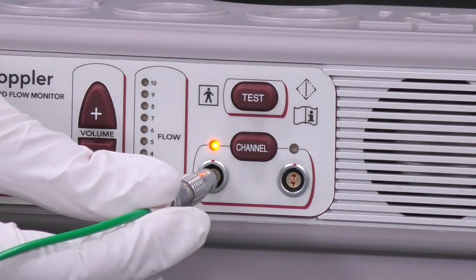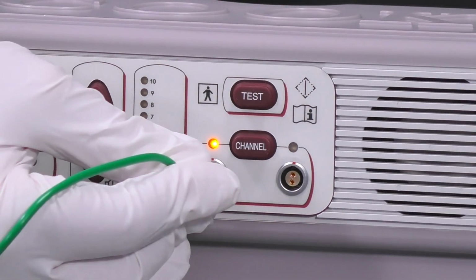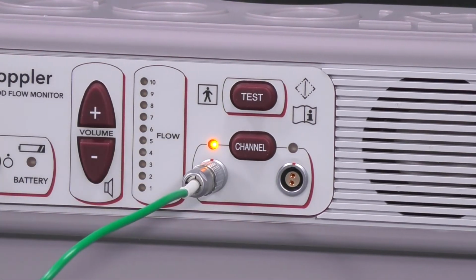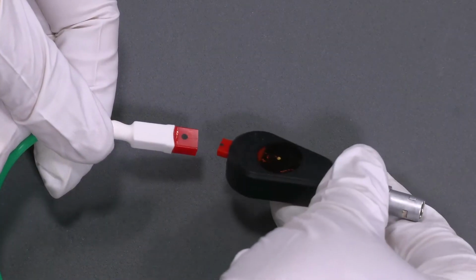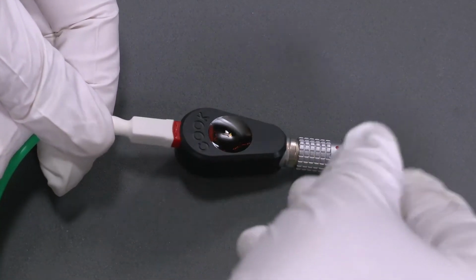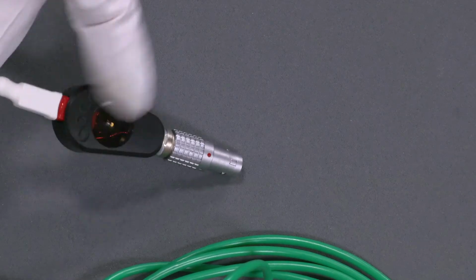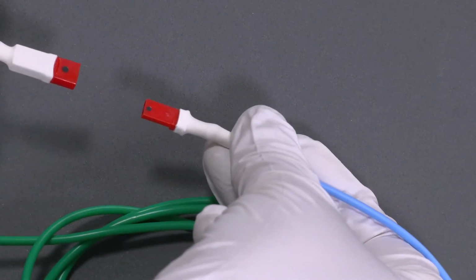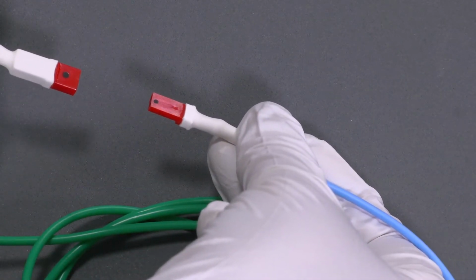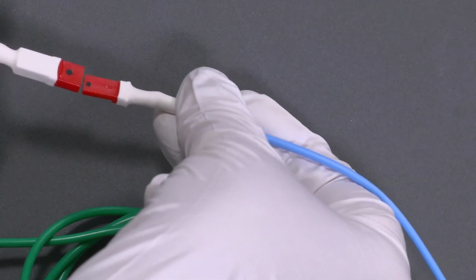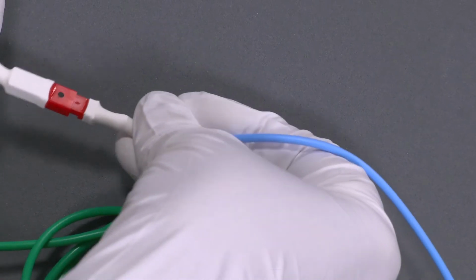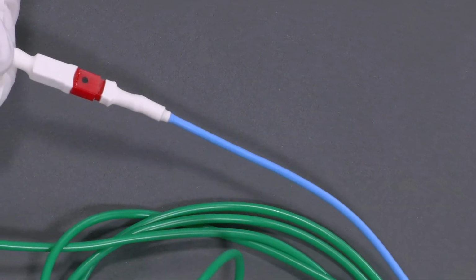Attach the metal connector end of the extension cable into the channel that shows the Doppler monitor is selected. Use the channel cable verifier to make sure that your extension cable is functioning. Attach the proximal red plastic connector of the probe to the distal red plastic connector of the extension cable. Make sure the black dots are aligned.